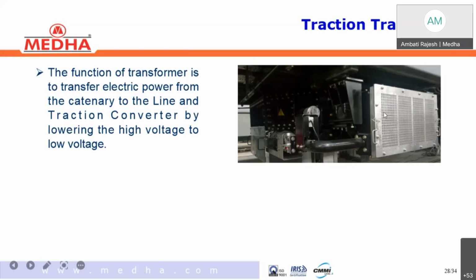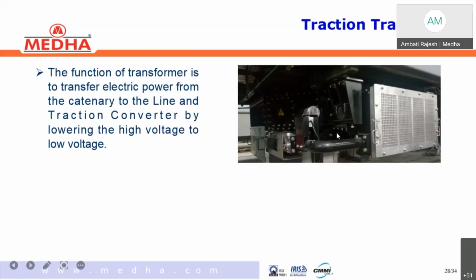This transformer is placed with 2 secondary windings: one primary winding which is connected with the OHE supply, and the 2 secondary windings whose output will be given to LTC. Each secondary winding output is given to one LTC line and traction converter. Okay, so this is about the traction transformer. In MEMUs, in general, it is taken from ABB and Siemens make. During motoring it acts as a step down transformer, but during braking it works as a step up transformer. Okay.